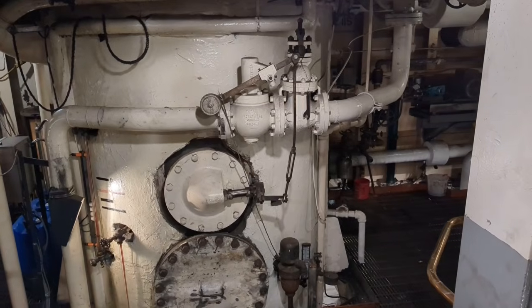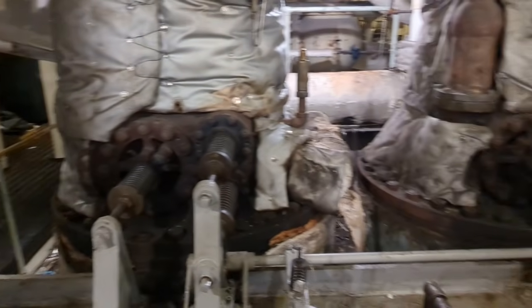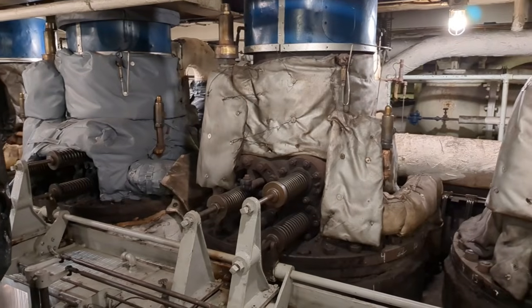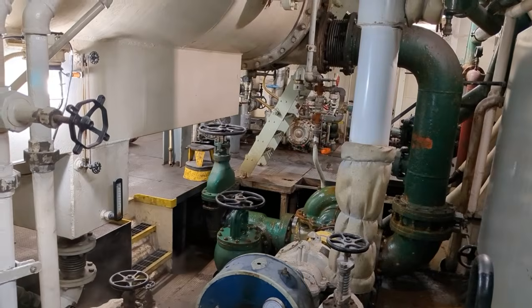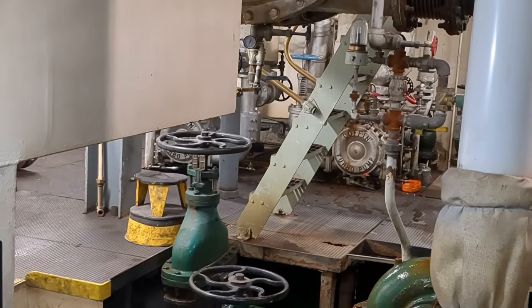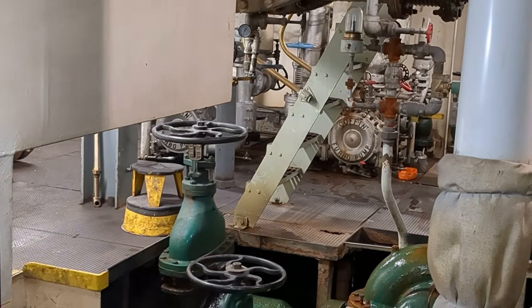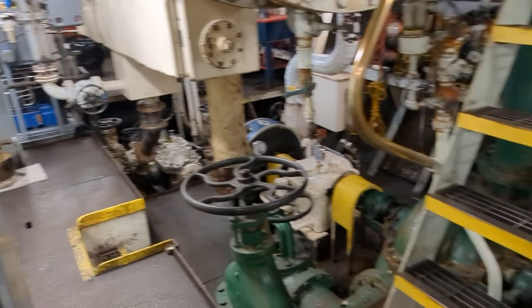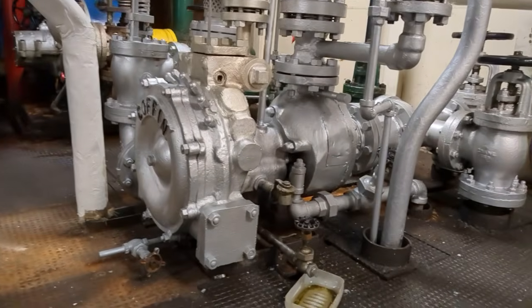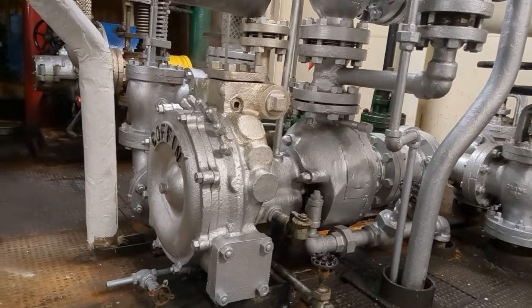The filtered water then enters the deaerator where it is mixed with exhaust steam from the circulating pump turbines. This heats the water and removes dissolved air before it returns to the boilers. Below the deaerator are the feedwater pumps. While many steam plants use large multi-stage pumps, the Badger uses a Coffin turbo pump.